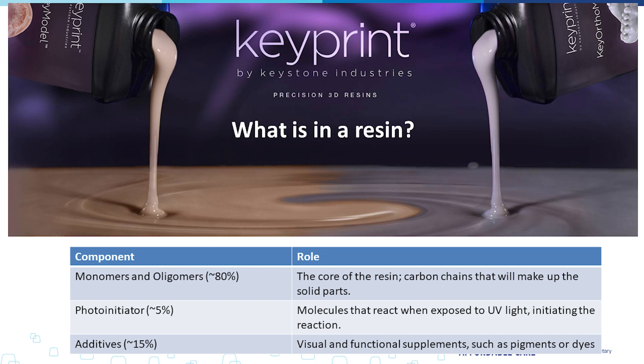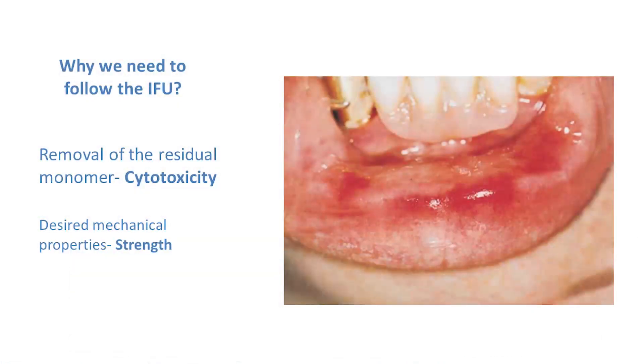Let's talk about what's inside these resins so we can understand where some of this porosity comes from. Resins are made up of three main components: the monomers and oligomers, which make up the majority of the material; the photo initiator, which is really the catalyst — the brains of the material; and the additives — dyes, fillers — things we add into the denture base and denture tooth material that give it color and additional strength. These three components, plus the printer, the cleaning step, and the curing box, all need to work in concert to create known results.